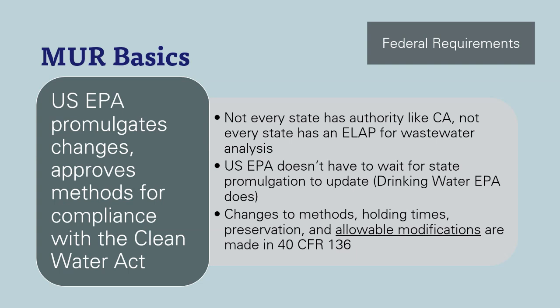Those methods are what they call promulgated or approved by the United States EPA, Environmental Protection Agency. Those are the agencies that control which methods are approved and disapproved for the Clean Water Act. So they write them into the federal rules in 40 CFR, Part 136. So for those who have an NPDES permit, you'll often see 40 CFR 136, and that's referencing where the analytical methods lie. It also has holding times and allowable modifications.